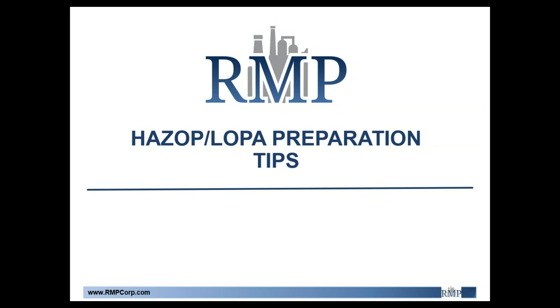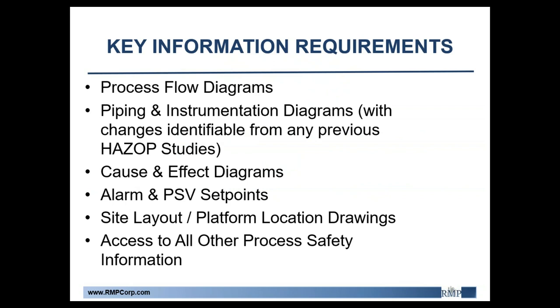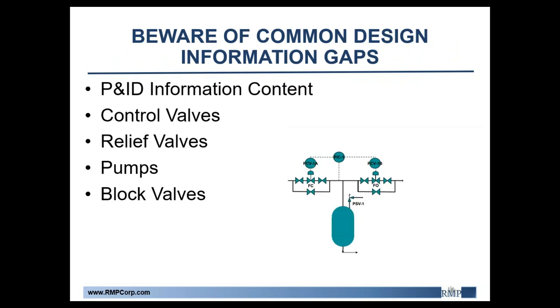For HAZOP and LOPA preparation, some key information requirements include process flow diagrams, P&IDs, cause and effects diagrams, alarm and PSV set points, and all kinds of other process safety information. A major setback for HAZOPs is time spent looking up key information — that valuable time can be spent focusing on the actual study as long as you're sufficiently prepared ahead of time. Things to consider compiling beyond the normal P&IDs include MOC and PSSR documentation, previous PHAs with their recommendations and current status, maintenance records, system descriptions, toxic chemical and physical properties, operating procedures, emergency procedures, and accident history.